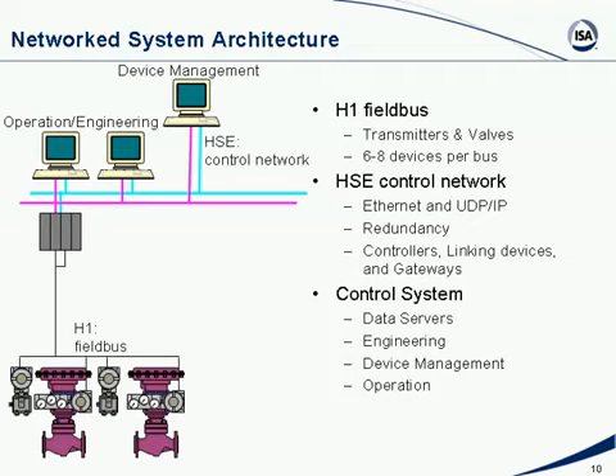Also at this point, I want to mention that other buses, there are many. Well, field bus has become a generic term really in the industry, but other buses are not the same as Foundation field bus. There are several differences. Okay, actually, Foundation field bus was specifically designed for process control. So for example, that includes features like separation of real-time and non-real-time communication. Okay, so there's actually a schedule that ensures that updates are precisely periodic, and also that the communication is synchronized with the control execution.